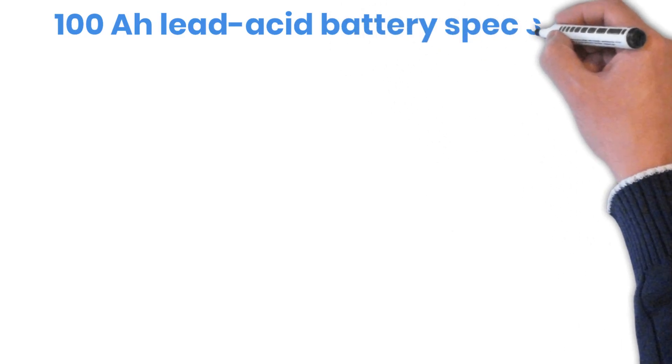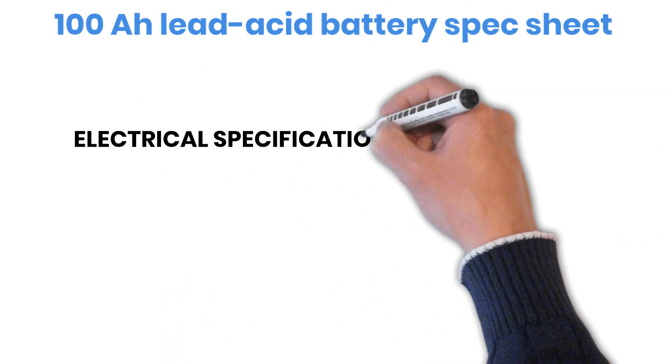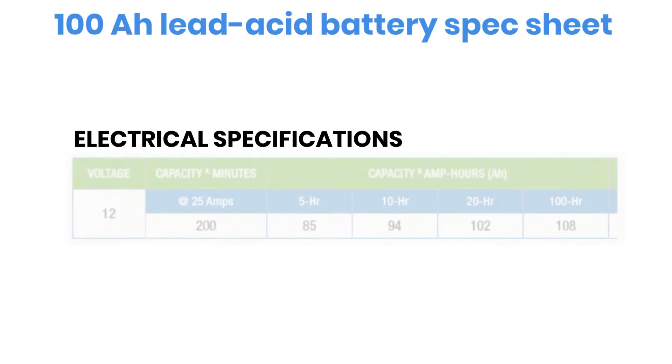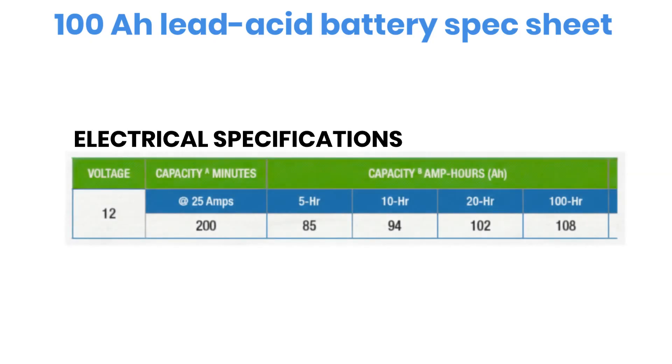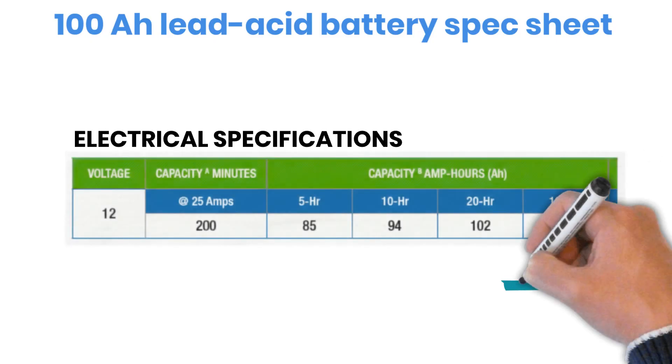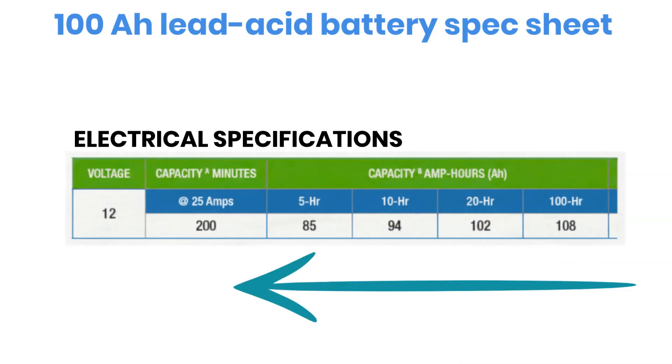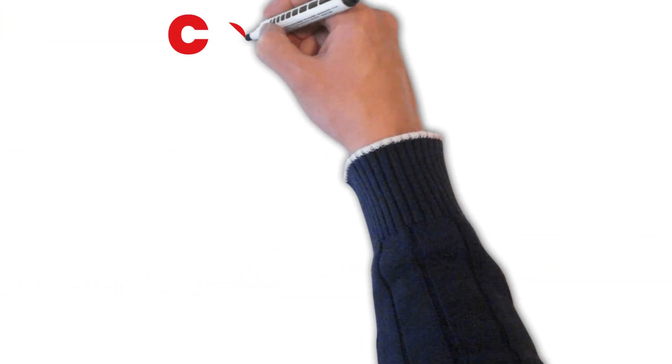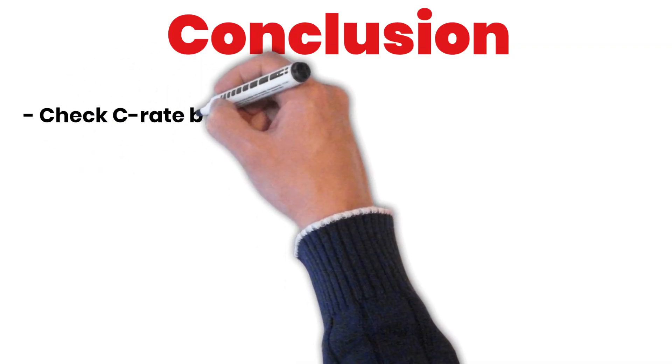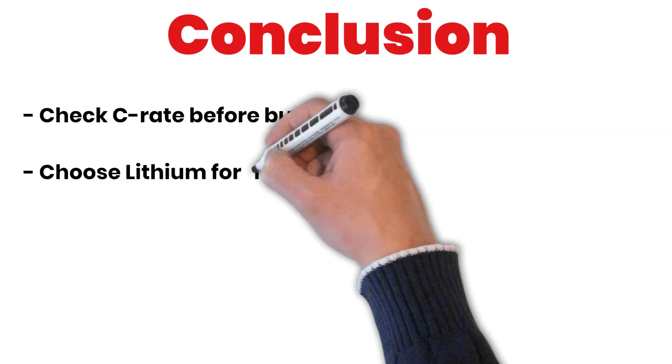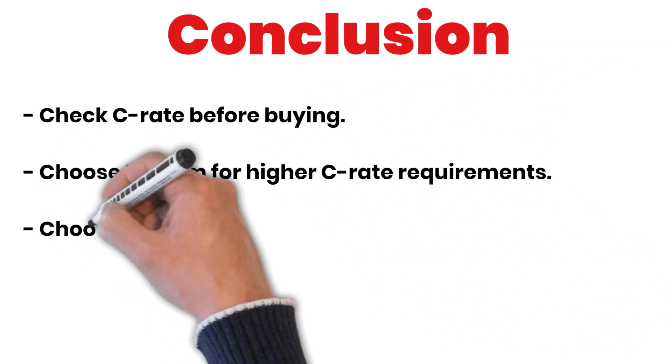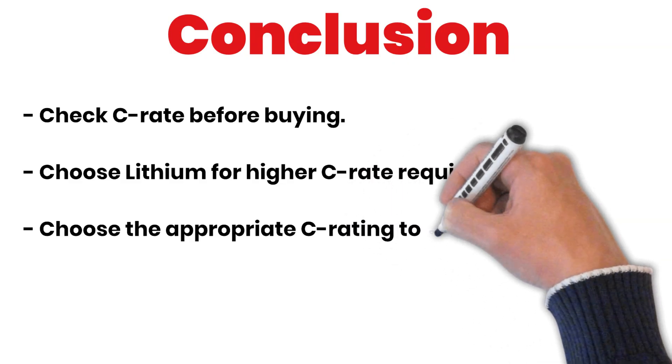Now let's talk about something most people overlook. When a lead-acid battery is discharged at a rate higher than its C-rating, its effective capacity drops. This happens because more heat is generated and internal resistance increases, making the battery less efficient. If you check the discharge graph for any good lead-acid battery, you'll see that higher C-rates lead to lower usable ampere-hours. That's why it's important to know the recommended charge and discharge C-rates before buying a battery for your solar setup. Lithium batteries generally support higher C-rates, while lead-acid batteries must be used within their limits to avoid premature capacity loss.